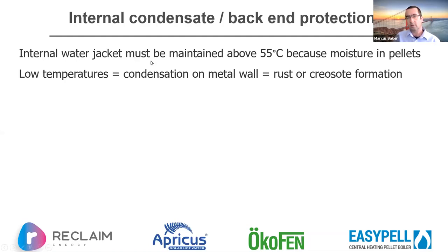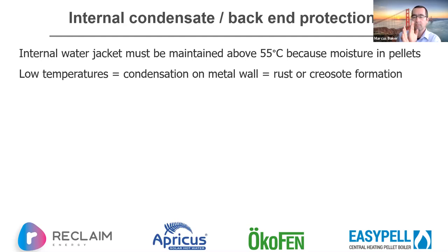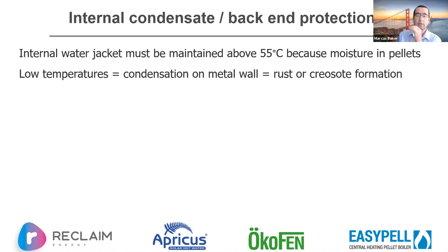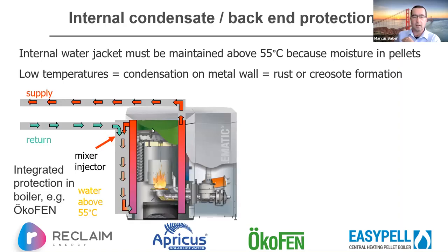Looking at the internals: the water jacket is really important. We're dealing with a biomass fuel — there is moisture in the pellets — so we must maintain the water jacket during combustion above 55 degrees. Otherwise you'll get condensation forming on the metal walls. Just like a wetback fire where cold water meets the hot firebox wall, condensation forms, leading to rusting and creosote formation — essentially destroying your boiler from the inside out. That's the absolute no-no in pellet boilers.